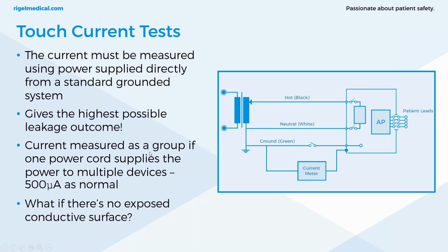There's also a statement in NFPA 99 on touch leakages when one power cord supplies the power to multiple devices, which is an interesting statement because, compared to other standards I've looked at, it avoids confusion when testing things like stack systems. That often causes a little bit of an issue when you've got multiple devices that are stacked and considered one system. It does cause a little bit of confusion. And here in NFPA 99, it kind of avoids that confusion.